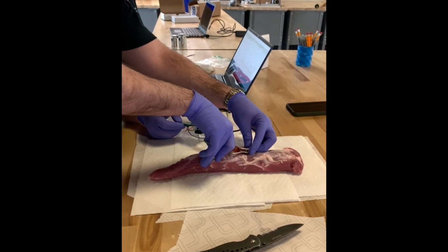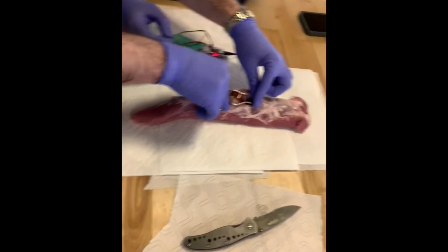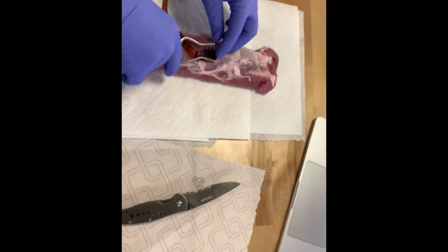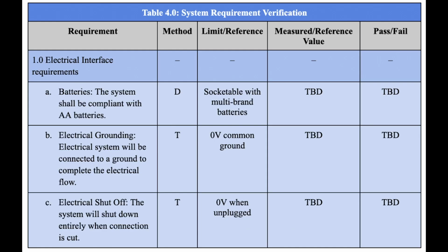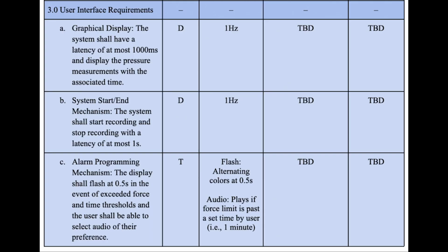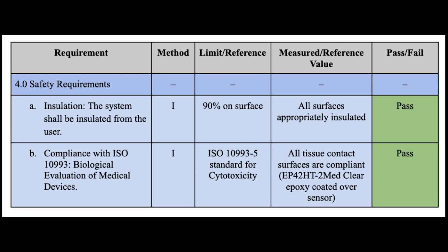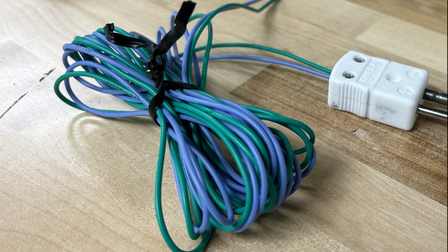The calibration curves mentioned previously were created through initial testing with pork shoulder, an exceptional analog to human flesh. The curves, as can be seen, demonstrate an excellent linear relationship to which we can calibrate the device. We split our verification procedures into sections to which they collectively best correspond, namely the electrical interface, user interface, performance, and safety procedures.